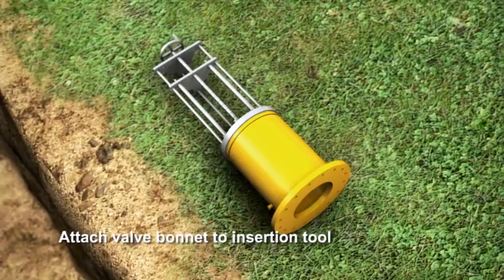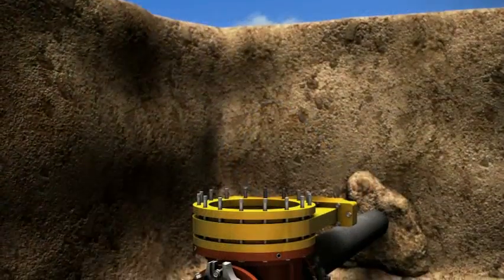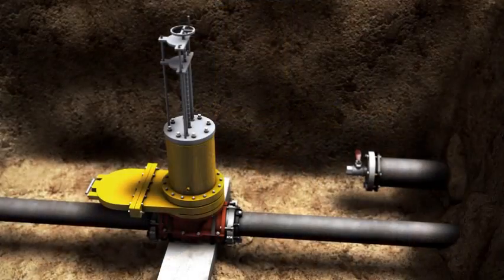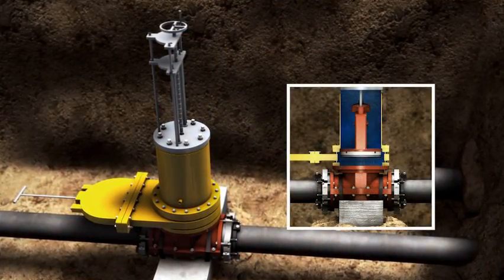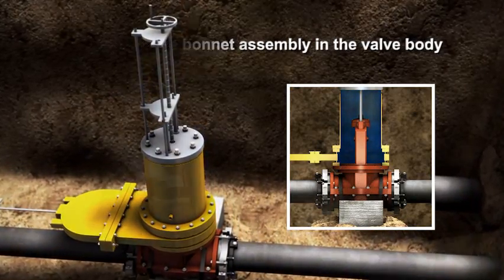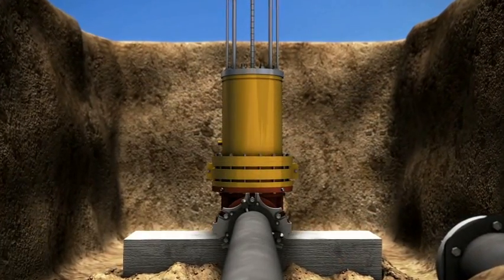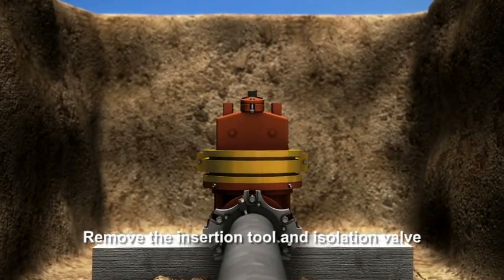This assures the owner of a clean valve seat. Close the isolation valve and remove the insertion tool. The valve bonnet is now placed inside the insertion tool. The insertion tool is mounted to the isolation valve. Open the isolation valve and advance the valve bonnet into the valve body. Through an internal equalization process, the bonnet can safely be advanced into the valve body. Mechanically advance the set pins of the valve body into the registration points of the valve bonnet.